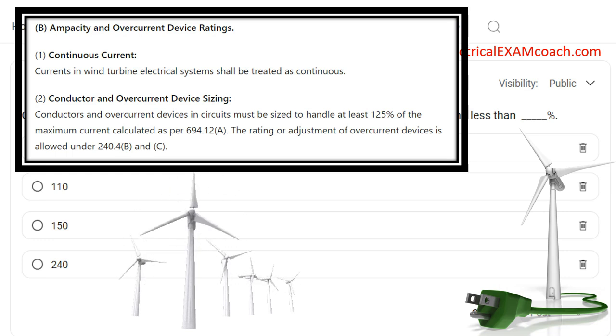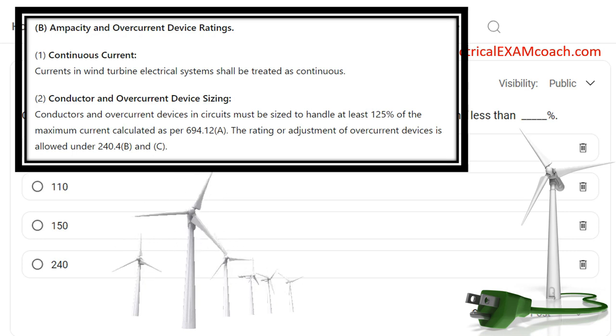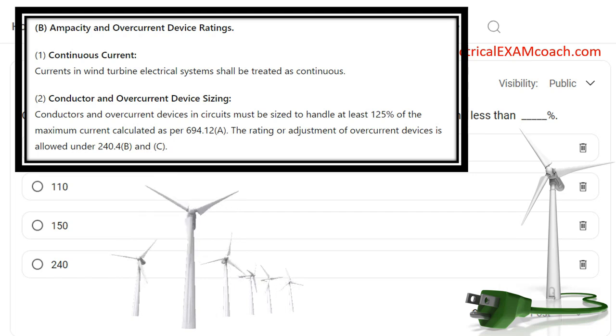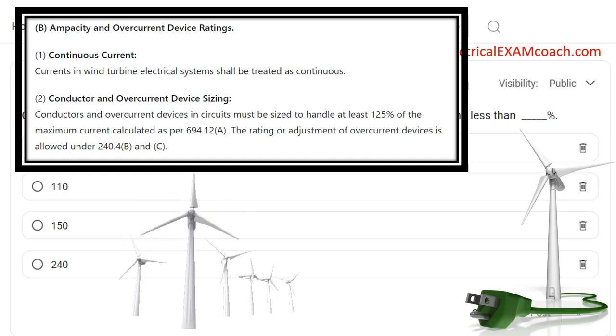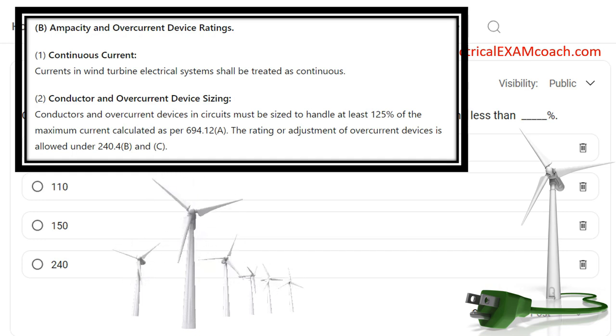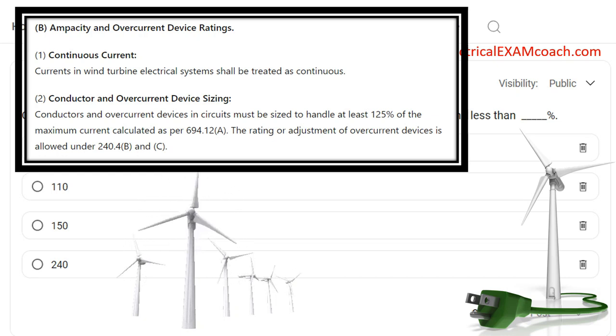The code also allows the rating or adjustment of the overcurrent device under sections 240.4(B) and 240.4(C). Those sections allow us, when the load is 800 amps or less, to protect the wire with a larger overcurrent device as long as we cover the known load — that's how we get the next-size-up rule. For example, if we had a known load of 94 amps and a wire rated for 95 amps, we could protect it with a 100 amp breaker. We've covered the known load, the wire is good for 95, and we're allowed to use the next standard size. That same rule applies here for wind turbines.